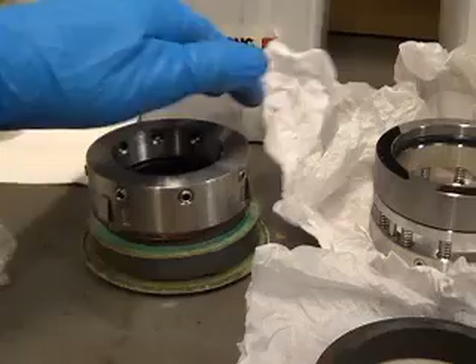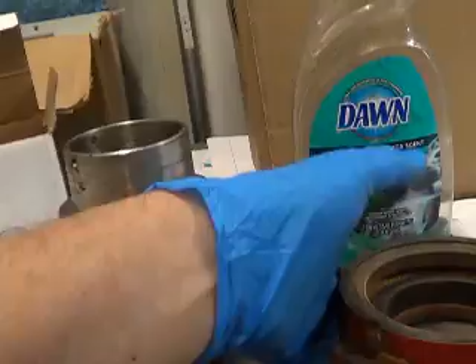On this one they do it a little different. This is older technology. You have the sleeve that goes over the shaft and is sealed, then your inner carbon seal, O-ring sealed inside, pressed and bottomed out. Then you've got this part, and this one was leaking. It doesn't look that bad, but the problem was all the rust and debris caught in the springs because it was on the water side.